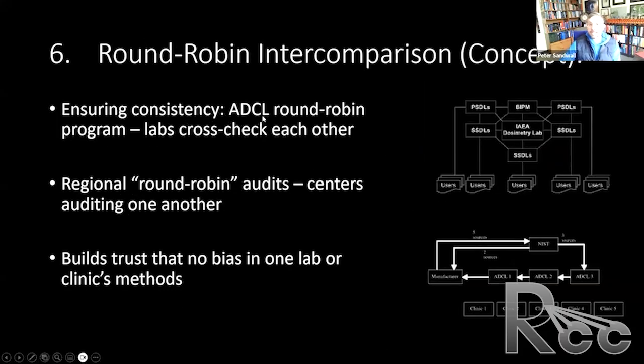So the way that the ADCL, these accredited dosimetry laboratories, actually verify that their equipment is working, that their calibration is correct, is that they audit each other. And they audit each other through what's called a round robin audit. Sorry for that, there's a loss in resolution, but this one in the lower, you can see they're looking at sources, but it's the same process. NIST, the primary calibration laboratory in the United States, will calibrate an ionization chamber, and then send it out to all the different accreditation laboratories, and we have 3 in the States. Everyone will do a calibration of the same chamber, and then they'll do a comparison. In the same way, the IAEA dosimetry lab will do that with their secondary dosimetry laboratories.